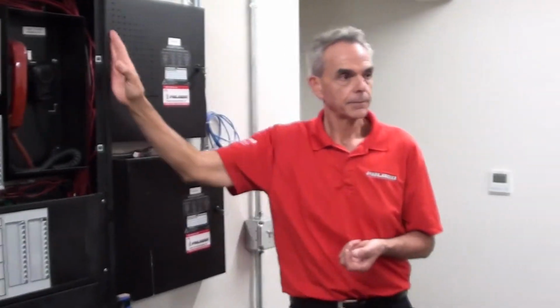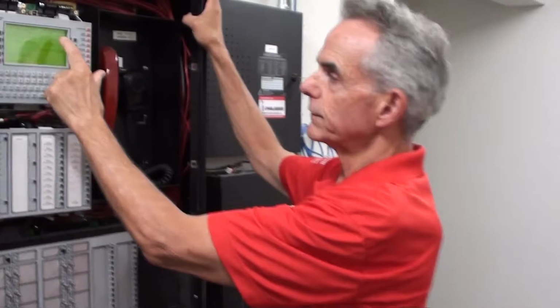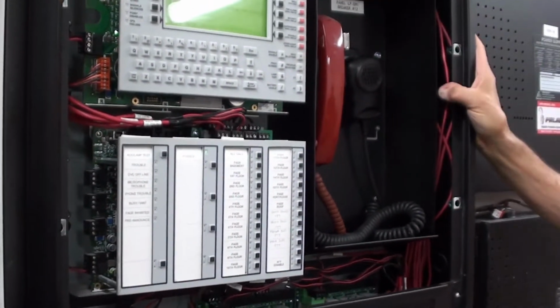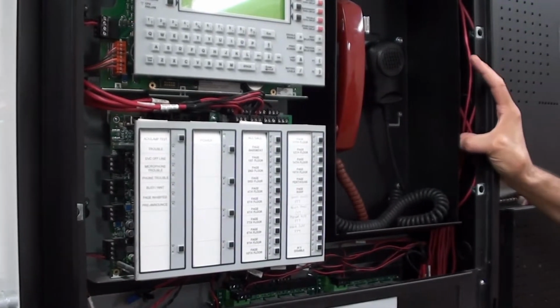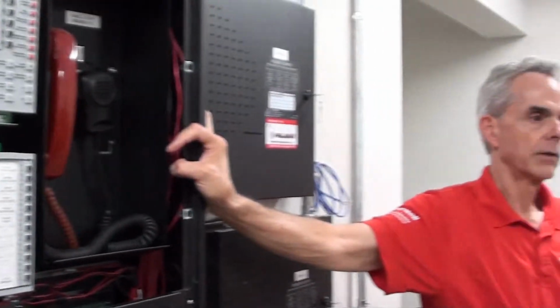Does it show what a duct detector is? It'll show where it is. It says right here, it's a south fire damper. It's on the 15th floor. So that would be in suite 20 in the kitchen, right? Yes, kitchen area. Other side of the slop sink, you've got the stairwell on the south side, then you have a slop sink, and then it's going to be in that first suite, right next to where the slop sink is.